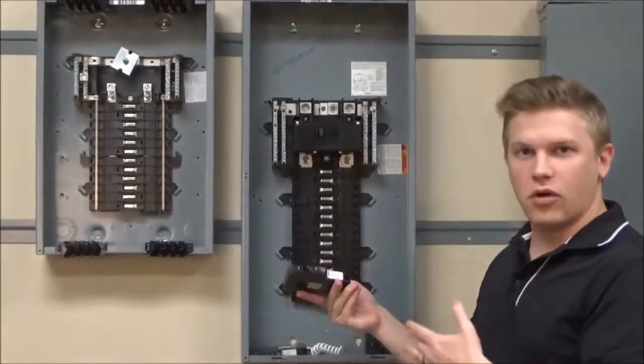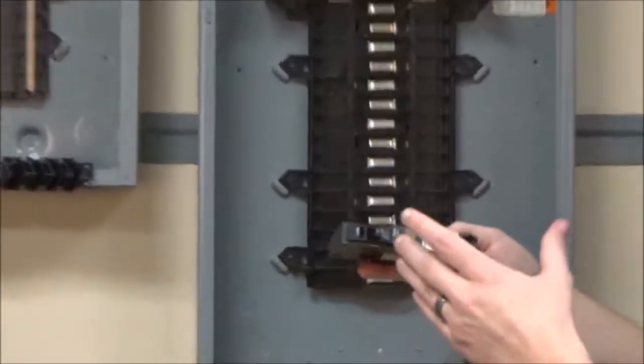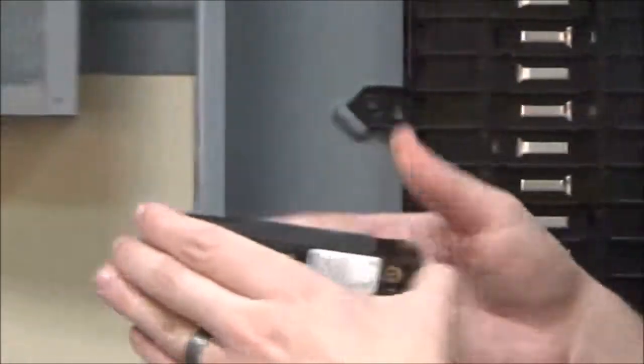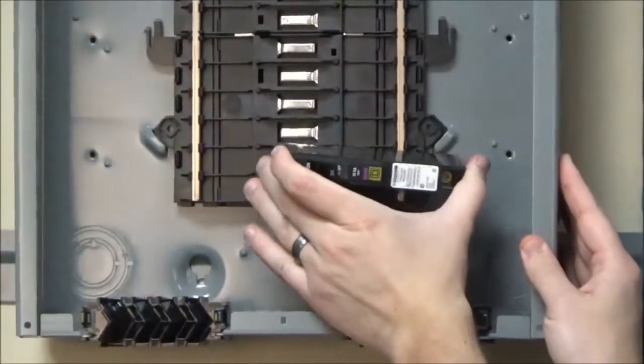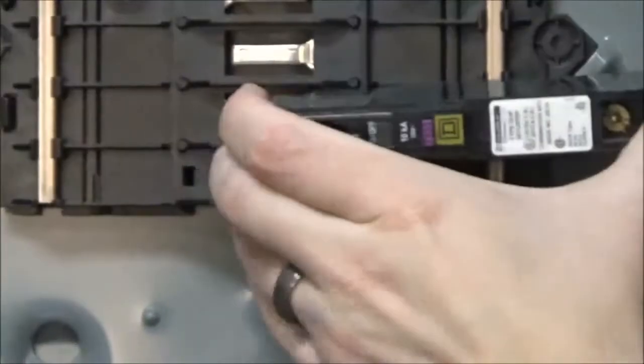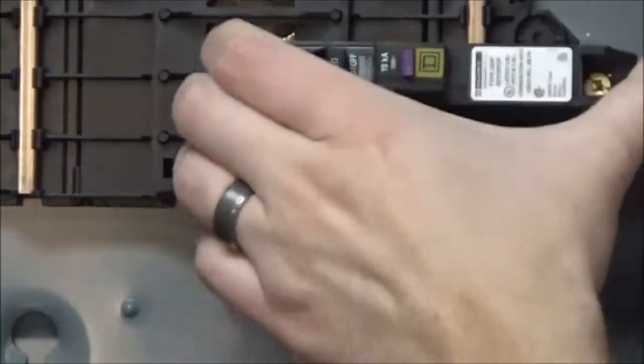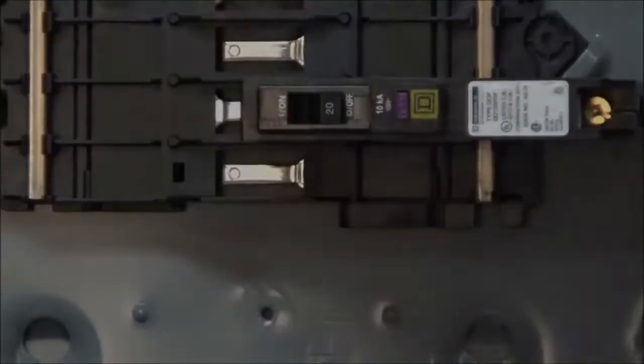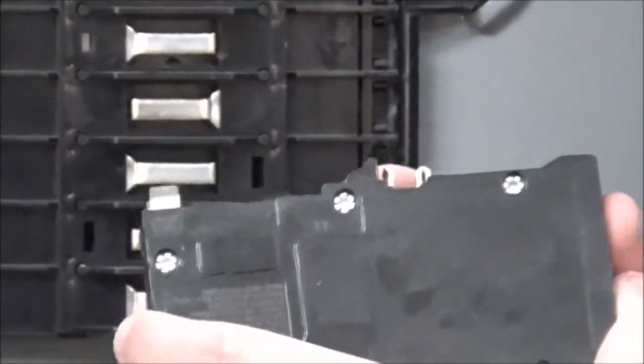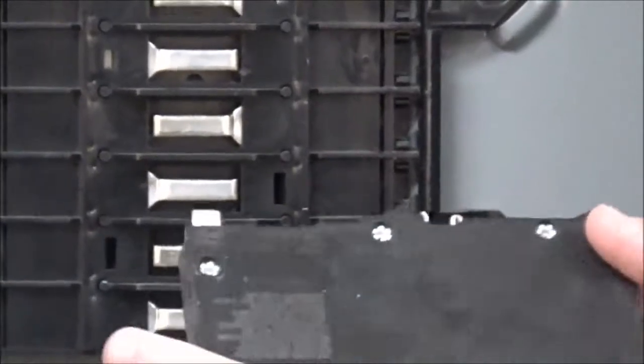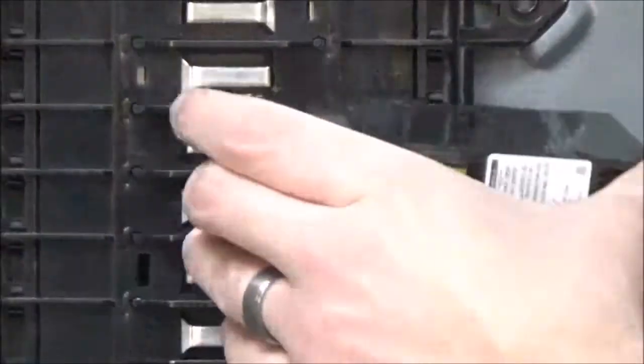The plug-on neutral arc fault breakers and dual function breakers will install on the plug-on neutral panel in a similar fashion. However, there is a rejection feature here that prevents the breaker from being able to be installed in a standard QO panel.